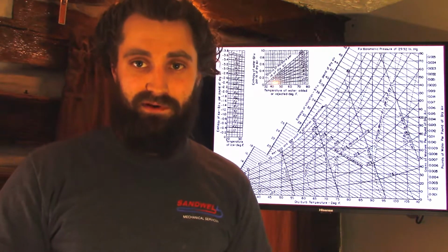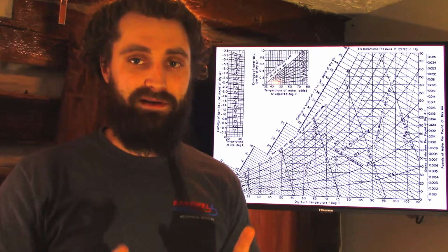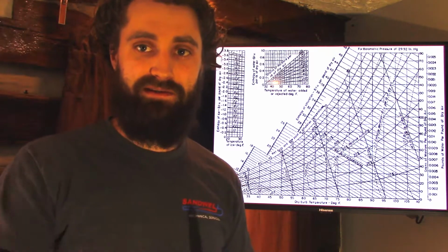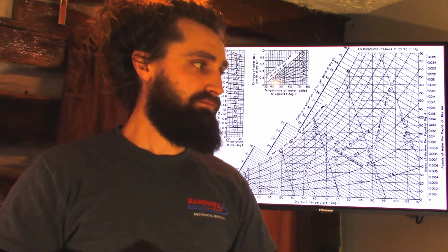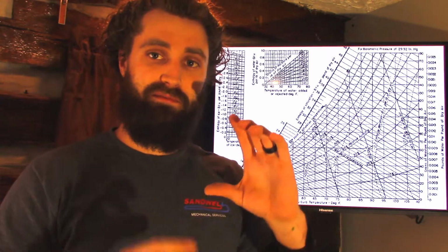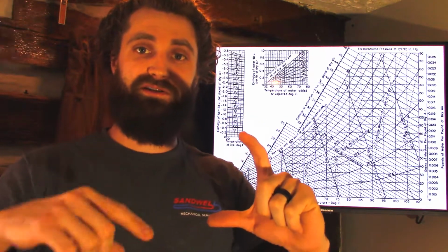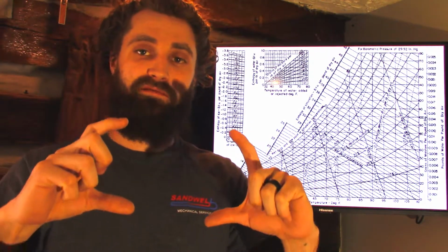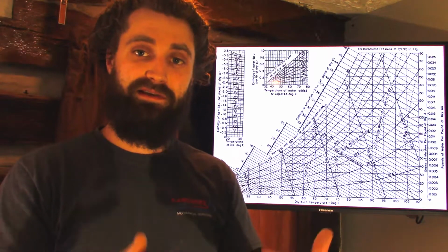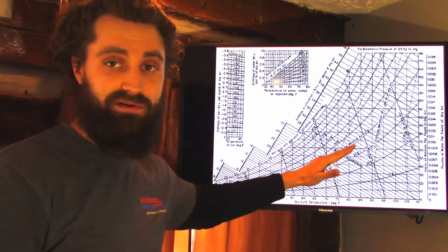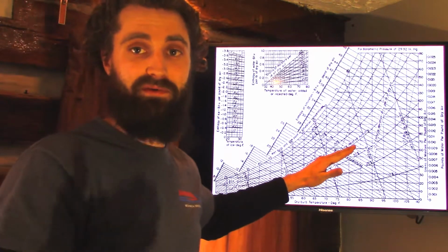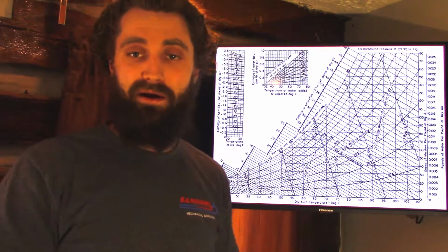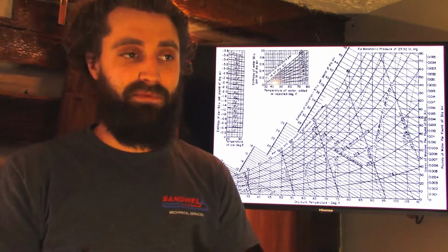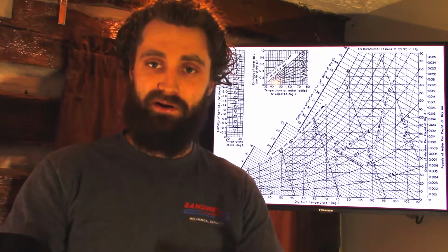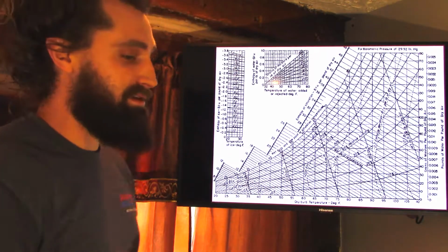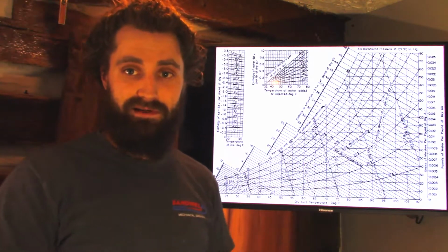Likewise, we don't want too small of a humidifier, because ideally it's only going to run whenever your HVAC equipment is running. I don't want to have to run the thermostat in the 'on' position just to maintain humidity. If the humidifier is too small, sized so that maintaining 40% requires it to run 24/7, that means our blower has to run 24/7 too. Any gains we got from adding humidity, we're just throwing money out the window because we're running the blower that much longer. So it's ideal that we size these things correctly.